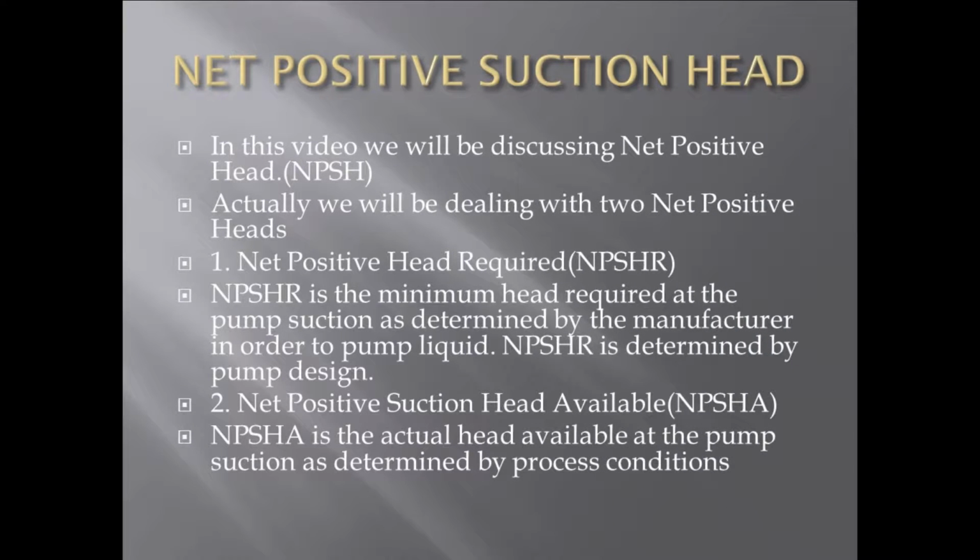In this video, we will be discussing net positive suction head. Actually, we will be dealing with two net positive suction heads. The first one is the net positive suction head required. This is the minimum head required at the pump suction as determined by the manufacturer in order to pump liquid. Net positive suction head required is determined by pump design.